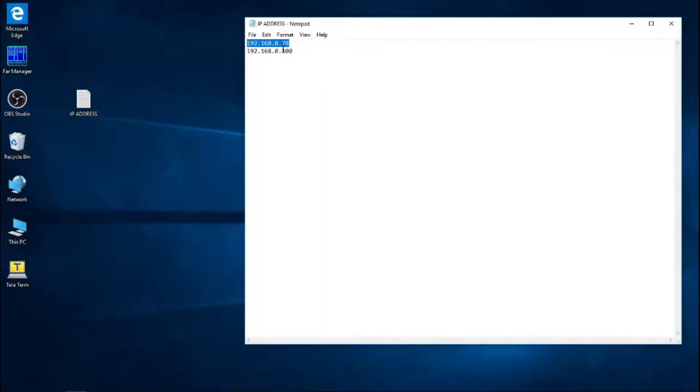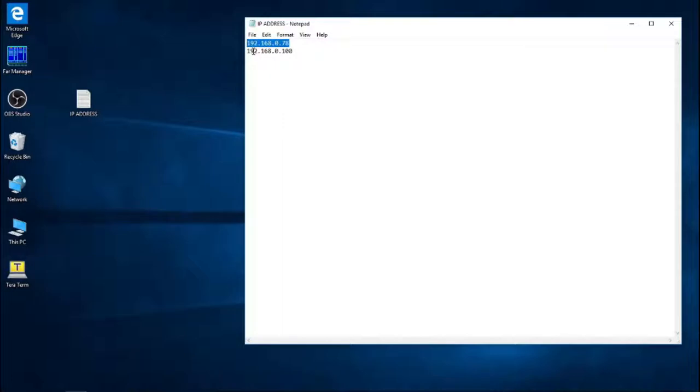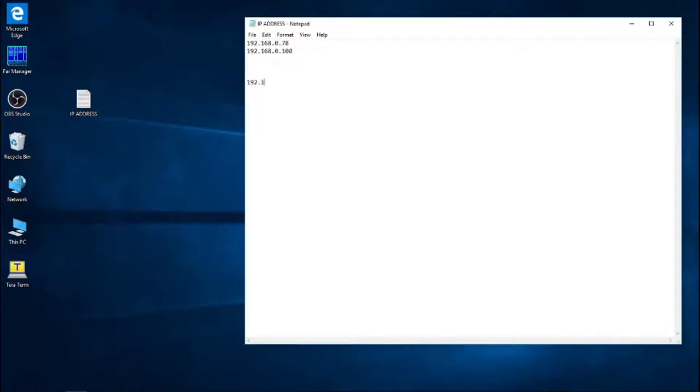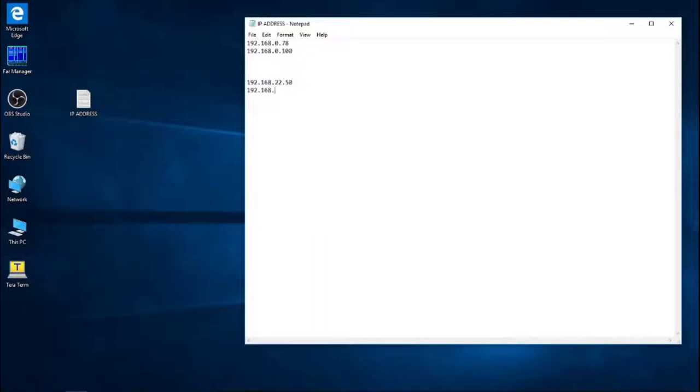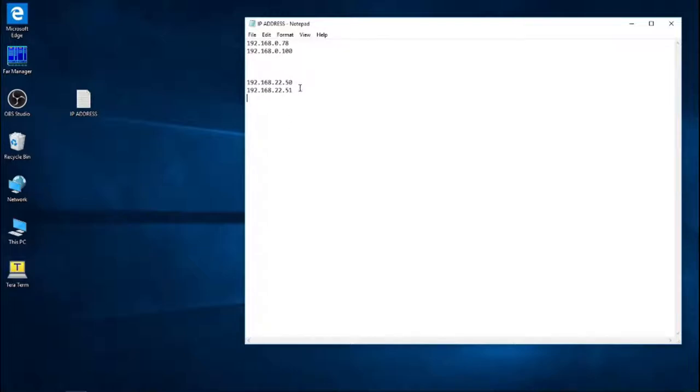Here are the two addresses that I used in the previous example. So 192.168.0.78 for the controller, and 192.168.0.100 for my computer. You can see that they were in the same subnet so that they could communicate. At this point we'll be changing the controller address to 192.168.22.50, and the computer address to 192.168.22.51. You can see that they're still in the same subnet, that means that the first three digits are the same, and the last fourth digit is different.